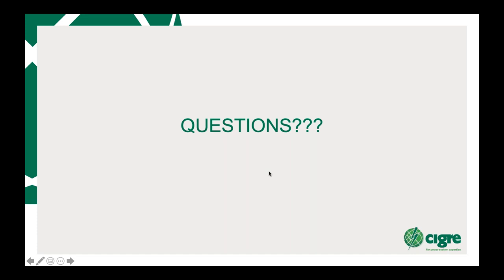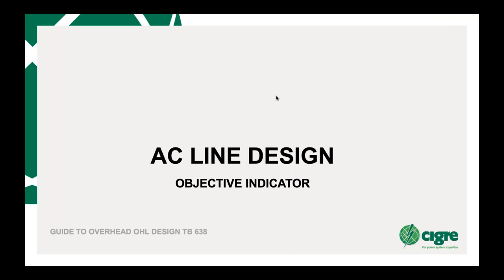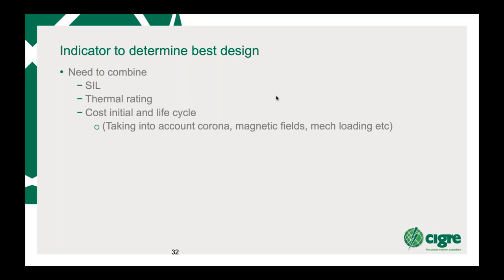Okay, now we're getting on to what we call an objective indicator. We've done everything now. We've got all these options. How do we put them all together? So we need to look at an indicator to determine the best design. So you need to combine surge impedance loading, thermal rating, and initial cost and life cycle cost of the line. And these would take into account corona.